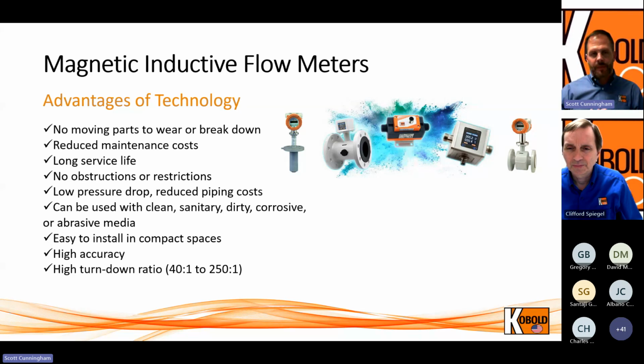Because of its compact nature, it can be installed in some tight spaces. It offers extremely high accuracy, and depending on the technology, a really high turndown ratio compared to traditional variable area or paddle wheel technology — either 40 to 1, or in some cases, like our small MIM, ranges up to 250 to 1. So again, a really high turndown ratio from minimum to maximum, where we can still give you an accurate measurement.